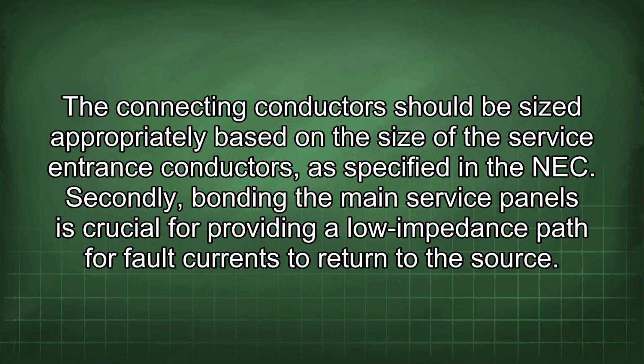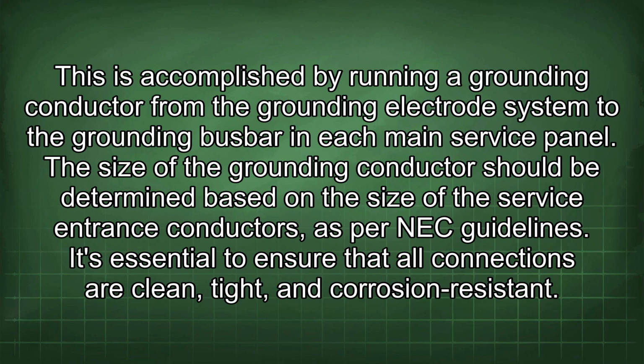Secondly, bonding the main service panels is crucial for providing a low impedance path for fault currents to return to the source. This is accomplished by running a grounding conductor from the grounding electrode system to the grounding busbar in each main service panel. The size of the grounding conductor should be determined based on the size of the service entrance conductors, as per NEC guidelines. It's essential to ensure that all connections are clean, tight, and corrosion resistant.